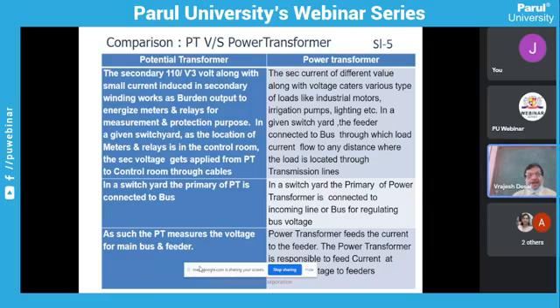The secondary output of the CVT, 110 by root 3, gets connected with the small current induced in the secondary winding. So it becomes 110 by root 3 into that current, which becomes a burden for the PT. This output is connected to meters and relays for measurement and protection purposes. We will further discuss this function also. In a given switchyard, the meters and relays are located in the control room, and the secondary voltage from the PT output is applied to the control room through cables.